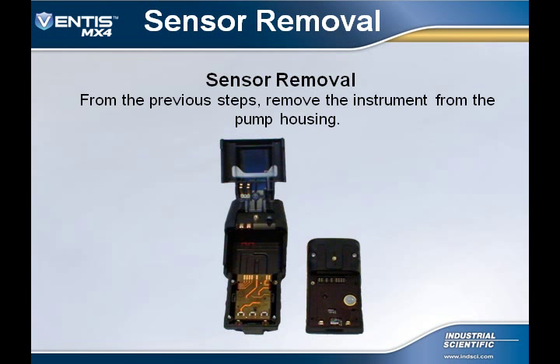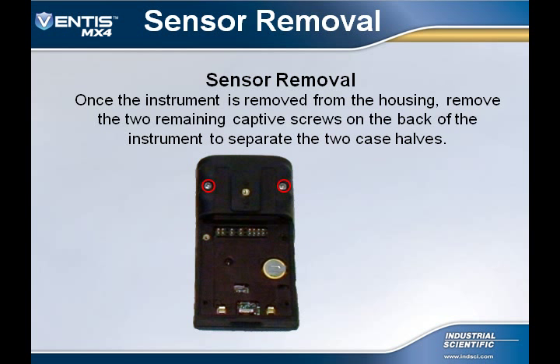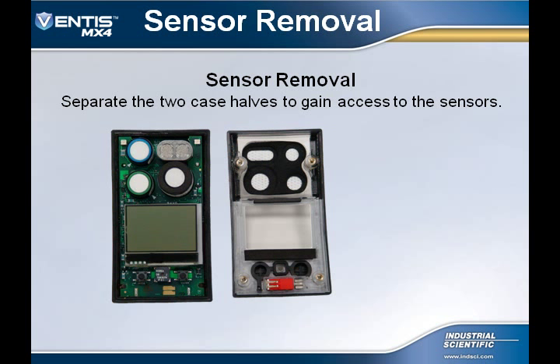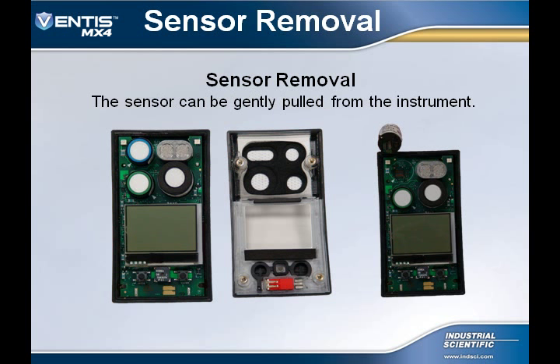To remove the sensor from the Ventis MX4, follow the previously mentioned steps, and once the 4 captive screws are loosened, remove the instrument from the pump housing. Rotate the instrument on its back and remove the 2 remaining captive screws. Separate the 2 case halves to gain access to the sensors. Simply pull the sensor from its connection.